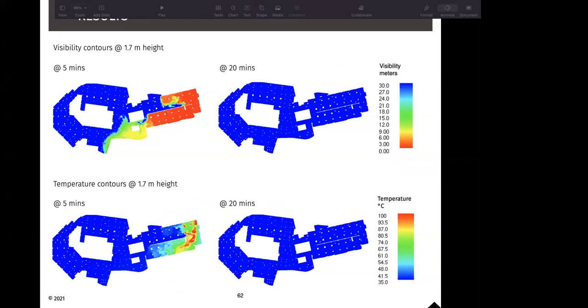Again, looking at visibility and temperature contours, we get full visibility by 20 minutes, and our system is back to ambient conditions within 20 minutes. So we can test for car parks or for any other system whether there is any kind of smoke accumulation, whether our system is extracting the smoke in a timely fashion, and whether the visibility is being maintained for a certain period of time before it is impaired, as well as for say a 20-minute duration, that can be studied with computational fluid dynamics.